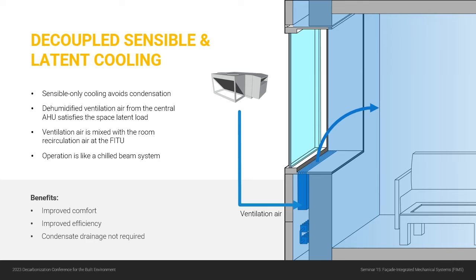And there are a lot of benefits to this: improved comfort, improved efficiency, and the fact that you just don't need condensate drainage. So when you're doing a retrofit, you don't have to worry about where you're going to route this condensate, how are you going to dispose of it. You save on the cost that you don't have to install a condensate drainage system. And even from a maintenance perspective, you're not worried about cleaning condensate drains or having clogged drain lines.